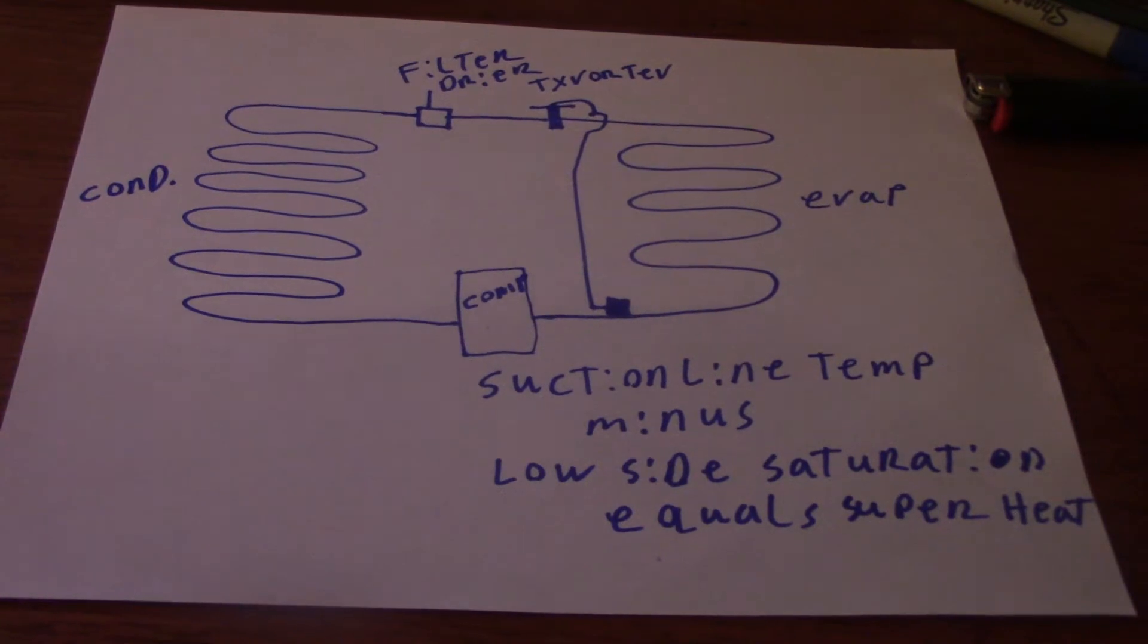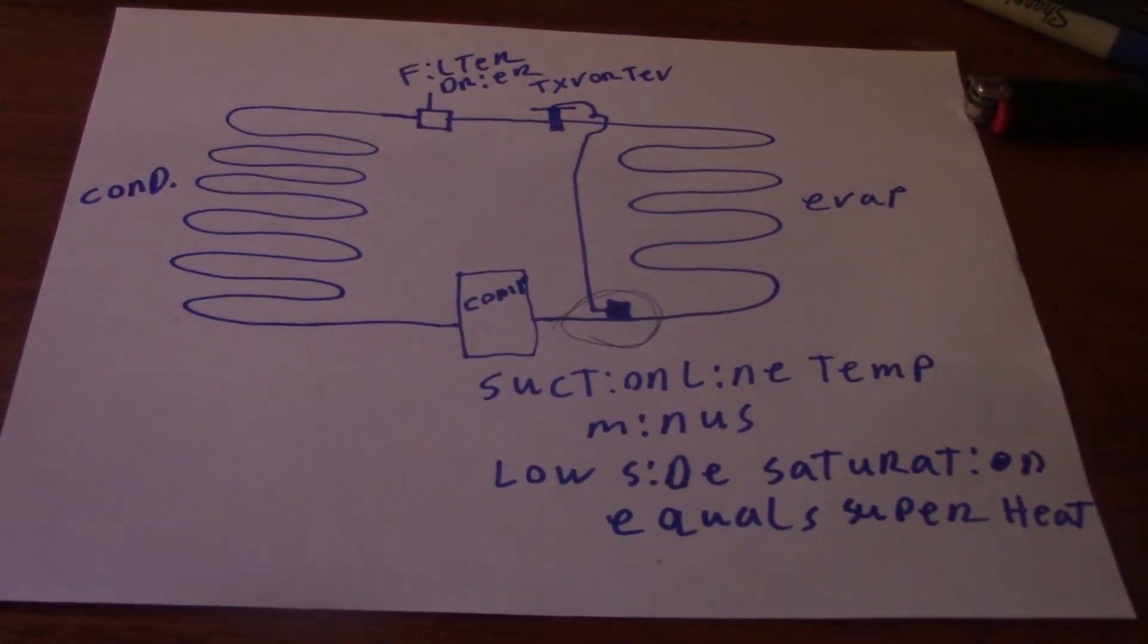Essentially you're going to take a superheat measurement for suction line temperature and pressure right in this area on the low side of the system. For more accuracy you want to be as close to that sensing bulb for your TXV as possible.